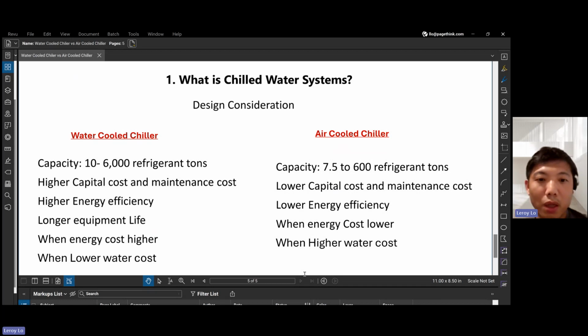And number four, another design consideration. When energy costs are lower, you can use the air-cooled chillers, but when energy costs are higher, you might need to use a water-cooled chiller since it's more efficient. This is from the efficiency standpoint. And number five, when water cost is lower, then you can use a water-cooled chiller. Definitely, it has a lot of water consumption. When you're using a water-cooled chiller, you have a cooling tower, which is a big factor for that. But when water cost is higher, maybe you need to avoid the water-cooled chiller. You use the air-cooled chiller for that.